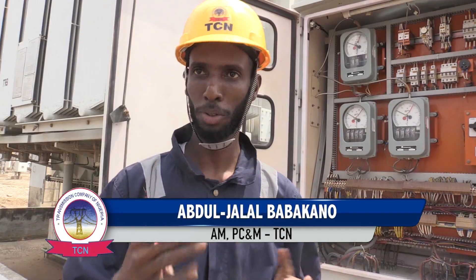So we have an annual maintenance plan for all of our systems, all of the transmission substations and all of the power lines. We have a stated date for every equipment and every line. We do it annually to ensure our equipment is functioning well and healthy, so that whenever we detect any faults, we can maintain it ahead of time and avoid a total breakdown, because the system requires stability and you don't allow your equipment to fail. You need to maintain it to ensure everything is fine ahead of preventing breakdown.